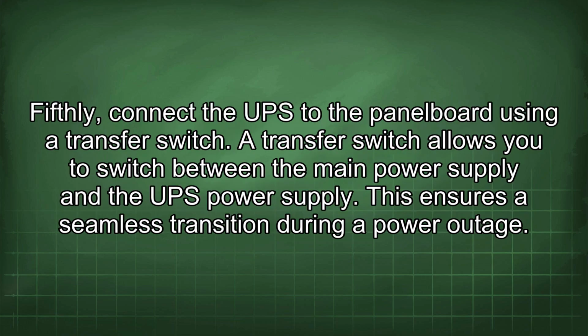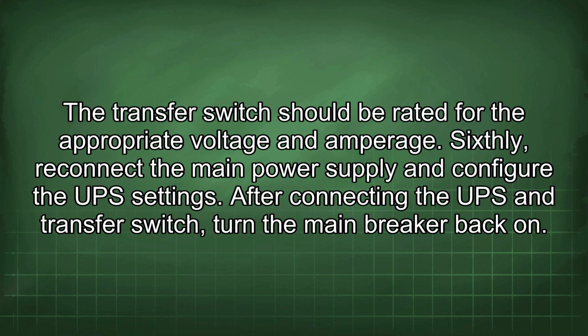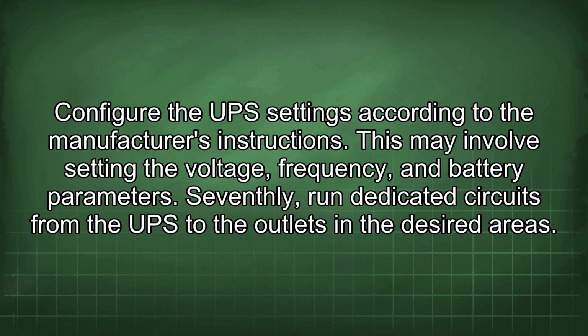Fifthly, connect the UPS to the panel board using a transfer switch. A transfer switch allows you to switch between the main power supply and the UPS power supply. This ensures a seamless transition during a power outage. The transfer switch should be rated for the appropriate voltage and amperage. Sixthly, reconnect the main power supply and configure the UPS settings. After connecting the UPS and transfer switch, turn the main breaker back on. Configure the UPS settings according to the manufacturer's instructions. This may involve setting the voltage, frequency, and battery parameters.